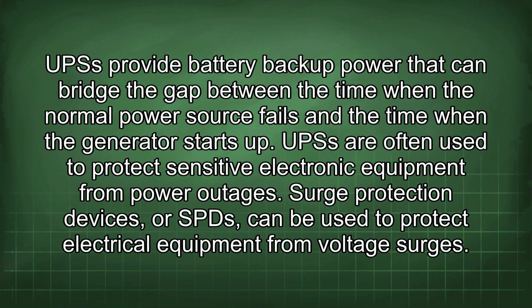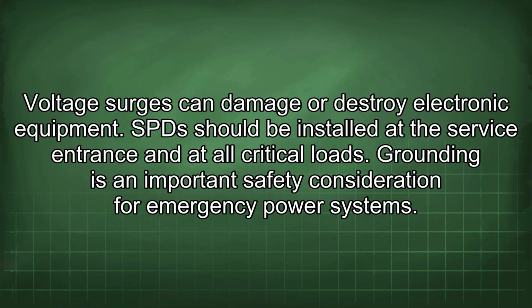UPS provide battery backup power that can bridge the gap between the time when the normal power source fails and the time when the generator starts up. UPS are often used to protect sensitive electronic equipment from power outages. Surge protection devices, or SPDs, can be used to protect electrical equipment from voltage surges. Voltage surges can damage or destroy electronic equipment. SPD should be installed at the service entrance and at all critical loads.